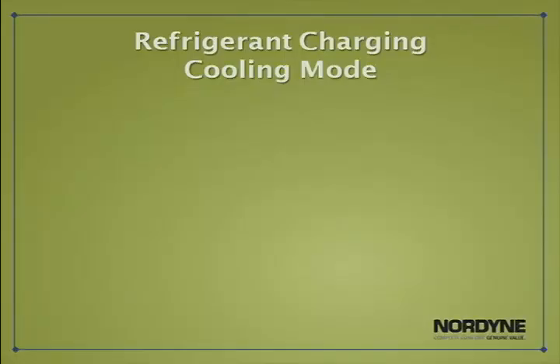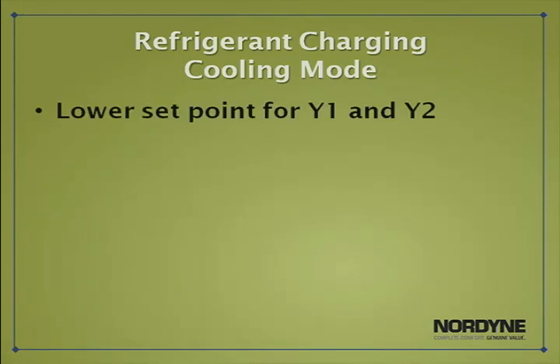To check the charge in cooling mode, you'll want to lower the set point on the thermostat so it calls for Y1 and for Y2. The condenser will start and run at stage C4, which is nominal capacity. C4 will run for 45 minutes. This 45-minute stage time is your opportunity to test your charge level.